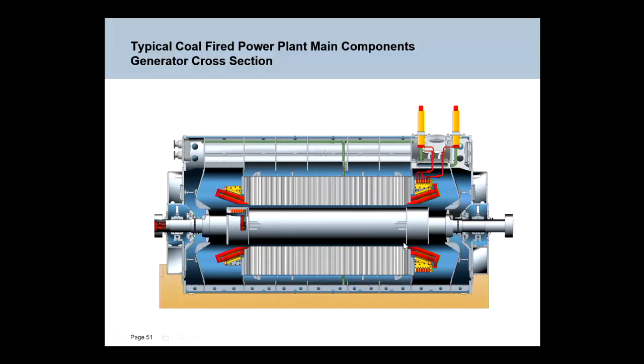The rotor, this part in here, this is what's driven by the turbine. It's spinning in Australia at 3,000 RPM. It has windings in it, so it is a rotating electromagnet with 2 poles. As it spins, those lines of electromagnetic force cut the stator windings and induce a flow of current. Okay, for those of you that did physics, Lenz's law, induce a flow of current that goes up and out of these connections and out to the grid.